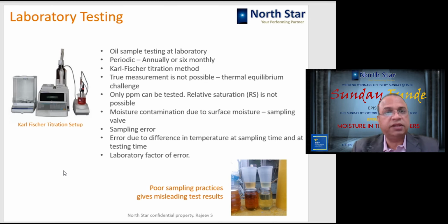There is nothing wrong with the Karl Fischer titration or doing this test on the transformer, but the fact remains this. Another factor: when you are taking the sample from the transformer, there is a valve on the transformer which is exposed to the outside atmosphere and subjected to environmental factors including moisture. So when you take a sample, that moisture also goes into the oil sample, and when you test this sample for ppm, you are bound to get a high ppm value.